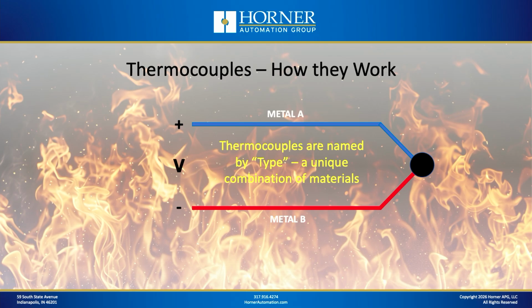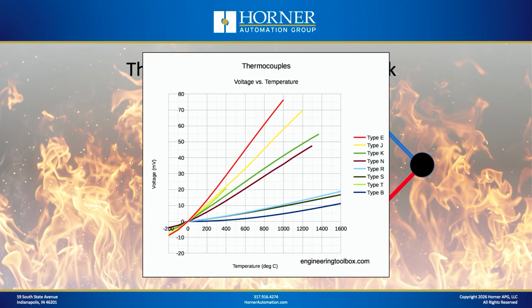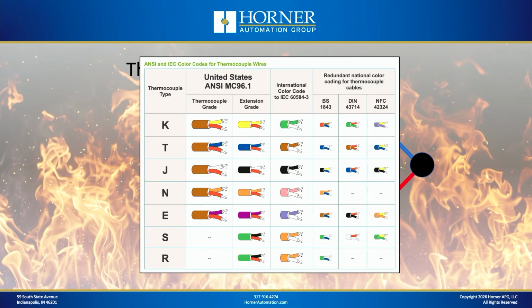And then the type of thermocouple that you would use for a given application is going to be named based on the different unique combination of materials that are used to construct that particular thermocouple. So different thermocouples with different combinations of metals will generate different voltage curves, if you will. And here's that voltage curve. And you can see that we're talking about some pretty small voltages here. In the case of some of the thermocouple types, the signal never gets above 20 millivolts, for instance. So that, again, is a pretty small voltage level we're talking about with thermocouples.